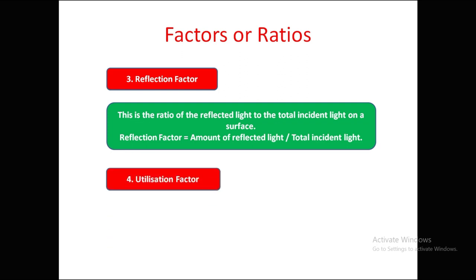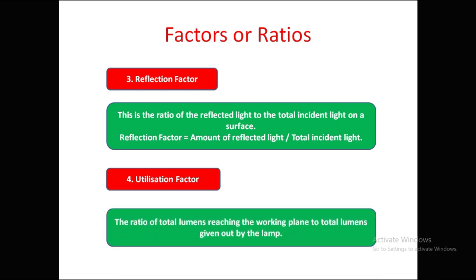Utilization factor is the ratio of total lumens reaching the working plane to total lumens given out by the lamp. Some energy from the lamp is wasted before reaching the working plane, and that ratio is the utilization factor.